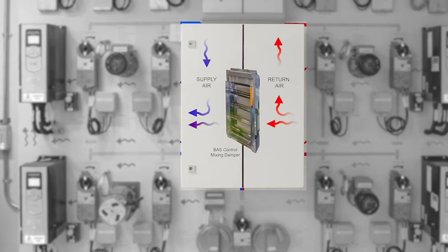In the event of the AHU unit losing communications over the embedded Modbus, manual control is available at the VSD units. A further enhancement was the installation of a jog button at the slim box. The jog functionality is limited in VSD software to low-speed operation at 5 Hz for a short duration of 5 seconds and is only available in hand control mode. It is designed to permit bump testing for function and direction following maintenance only.